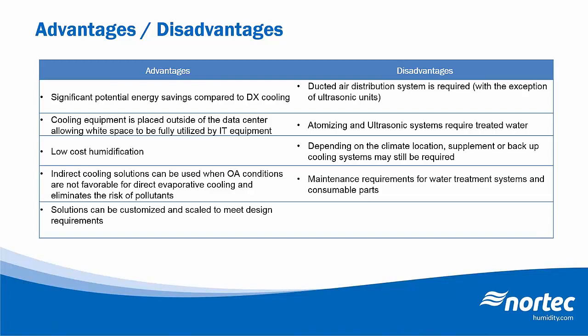Another disadvantage here is that in the event that the outside air conditions are not really favorable for economization, or there's a risk of outside pollutants, if there's a fire outside or there's smoke, supplemental backup cooling systems may still be required in addition to an evaporative cooling system. And last, not really a disadvantage, but just something that I wanted to mention here, is that maintenance for these types of systems is extremely important whenever you're using an adiabatic system. Not only to ensure the highest possible efficiency for the system, but also to ensure hygienic operation.